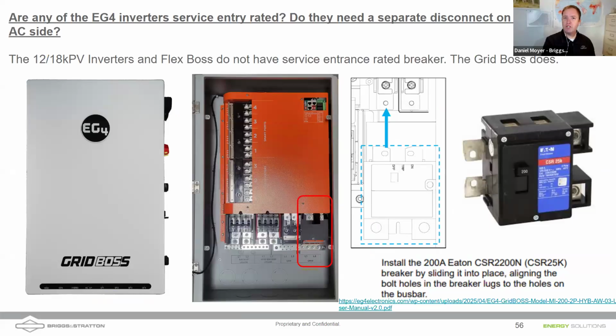I had another question: do any of the EG4 inverters have a service rated entrance disconnect? Our transfer switch is due on the generator side. The 18K and 12K PV do not, but the GridBoss does have a service rated entrance disconnect. Now, right out of the box, the Grid Boss does not come with this breaker. You got to go down to the supply center and buy the breaker. It's pictured on the right hand side, but you can insert this here and have it be the service disconnect.